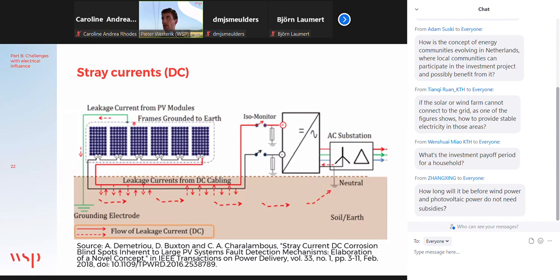But there is also always a bit of margin in this, because even the best cables will degrade a bit over time and start to leak a little bit of current, and this doesn't have to be a problem. So a little bit is always allowed, but these limits are usually based on fire hazard. They are trying to keep these leakage currents so low that there are no fire hazards. But that doesn't mean that these currents are low enough that they will not damage a nearby pipeline. So we really had to start looking at these systems in a different way and think about where the current can go into the ground.